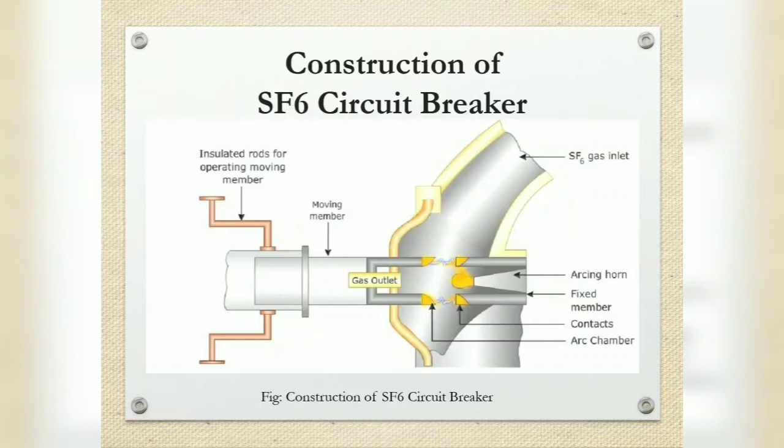The gas system. A closed circuit gas system is employed in the SF6 circuit breaker. The SF6 gas is costly, so it is reclaimed after each operation. This unit consists of low and high pressure chambers with a low pressure alarm along with warning switches.